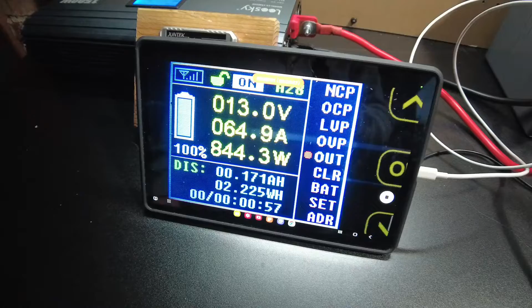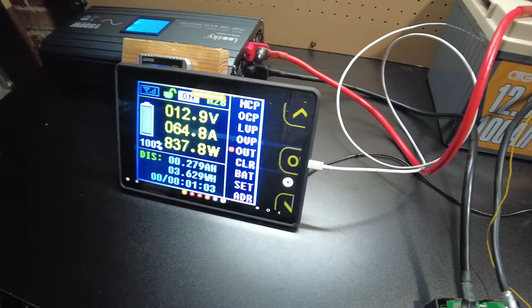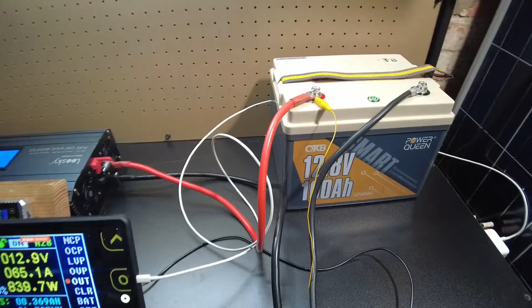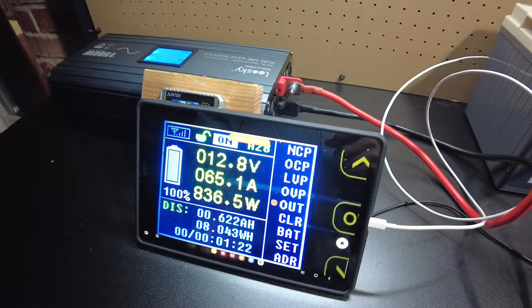We are drawing 64 amps, which is quite a bit more than a 0.2 C test. I typically skip the 0.2 C test because with lithium iron phosphate, there's very little difference between a 0.2 C and even a 1 C test. So it should pull full capacity. If it doesn't, we'll recharge it and do a 0.2 C test to give it one more chance. But anyway, we're going to let this run, and when it completes, I'll be back.